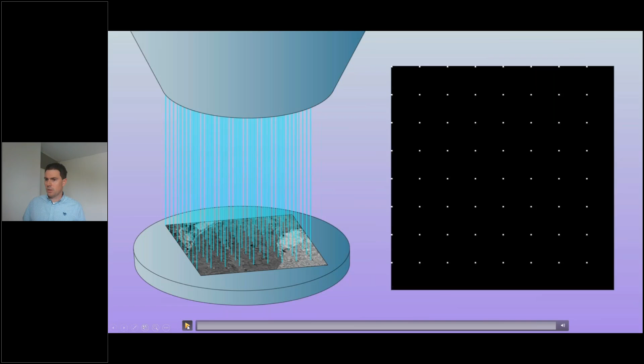The microscope is actually a modified version of a catalog microscope from Thermo Fisher. And they also did the modification with the multi-beam source, so that is further developed by Thermo Fisher. And as Technolution, we have developed the optical detection and data acquisition system, and combined that with the deflection controls of the electrons. In the next few minutes, I would like to focus on that combination of beam deflection and image acquisition, because if you do that right, the resulting process will look like this.